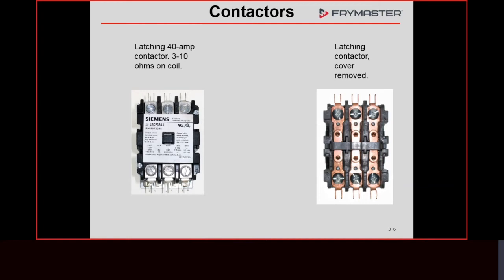If a latch contactor is switching current, that means we have an issue. Either we've got a shorted element or a stuck heat contactor. But with these, when they pull in, there should never be any arcing or anything like that because they're not switching any current. We've used these contactors as long as I've been here, which has been about 20 years, and they used them long before then for a latch contactor. Again, they should never go bad.